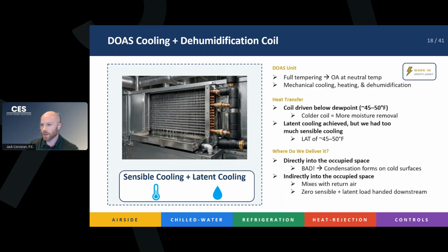So your DOAS unit is going to get, on the left side, that light blue, that very cold sensible cooling. And we're also going to get latent cooling, right? All that moisture comes off the coil. It's going to condense. The main difference between a DOAS unit and a regular air handler is that the coil temperature is much, much lower, right? We want to put the coil temp much lower than the dew point so that we can wring out the moisture as much as possible, right? A colder coil means more moisture removal, right?